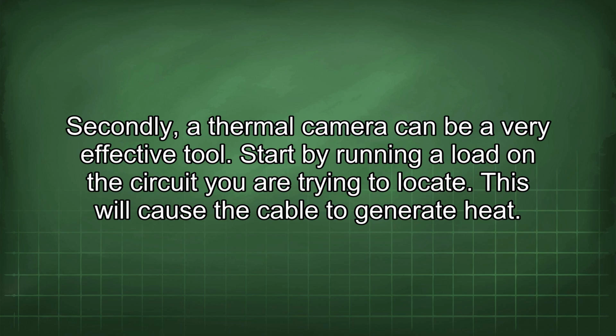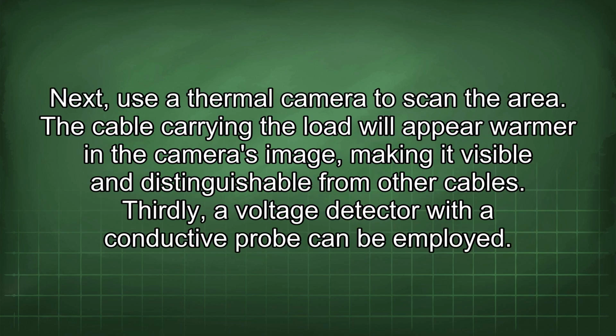Secondly, a thermal camera can be a very effective tool. Start by running a load on the circuit you are trying to locate. This will cause the cable to generate heat. Next, use a thermal camera to scan the area. The cable carrying the load will appear warmer in the camera's image, making it visible and distinguishable from other cables.